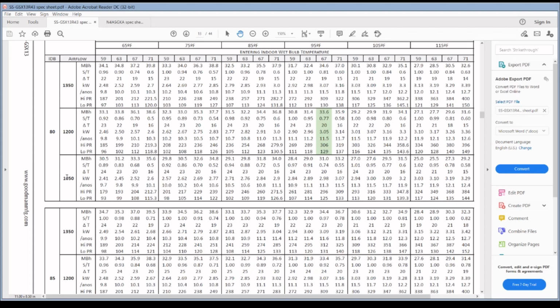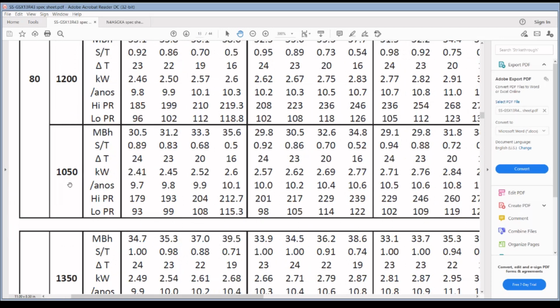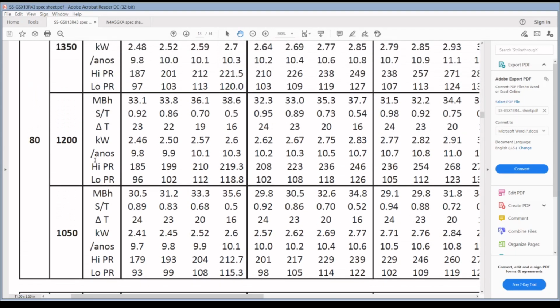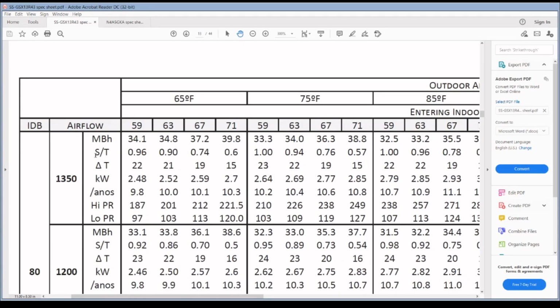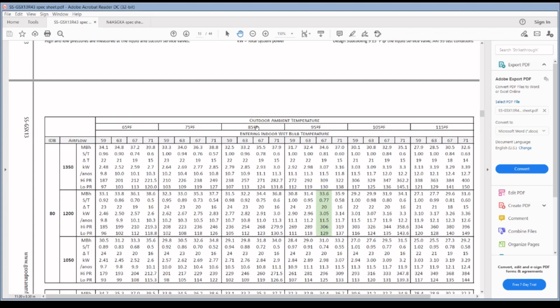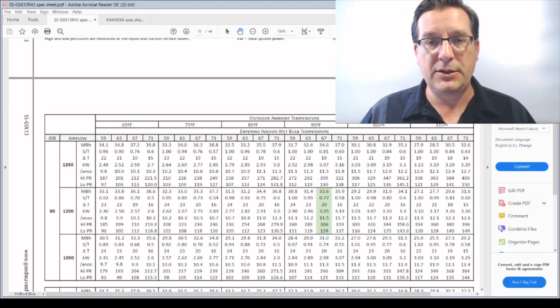We're given 3 different airflow selections. We have 1350 CFM, 1200 CFM, 1050 CFM. CFM stands for cubic feet per minute and has to do specifically with how much air is going across. So we go across the top, shrink this up again. As we go across the top, we have outdoor ambient temperatures. And this is going to basically tell us the specific performance of this particular AC plus coil combination at a variety of indoor and outdoor temperature conditions. So going across the top here, we have 65 degree outdoor, 75, 85, 95, 105, and 115.